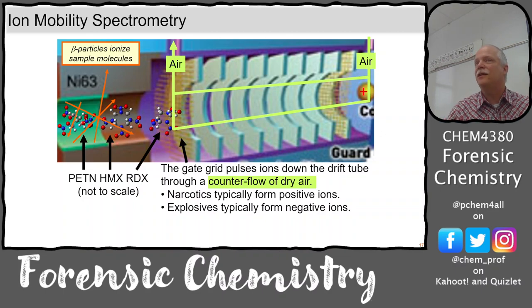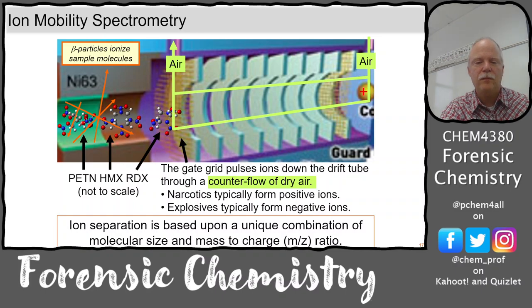We really want to detect both at airports, so they make a dual tube, like a T shape. You put in the sample, it goes up, gets ionized, and we have a positive detector on one end and a negative detector on the other. The narcotics and explosives go to their respective detectors, and we can detect both. Those are the second or third generation equipment.